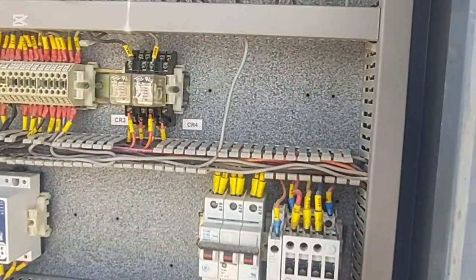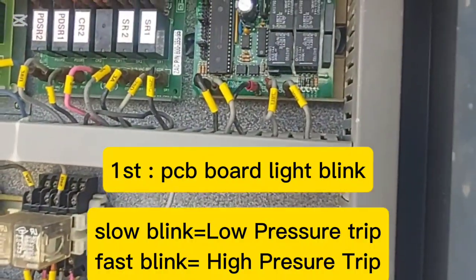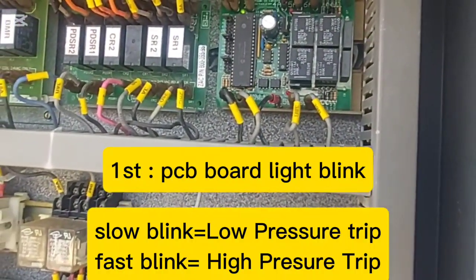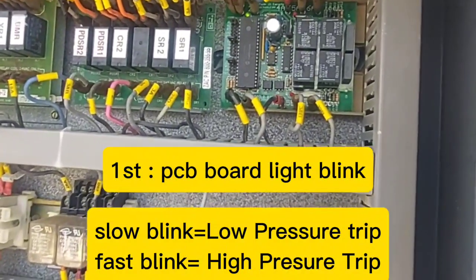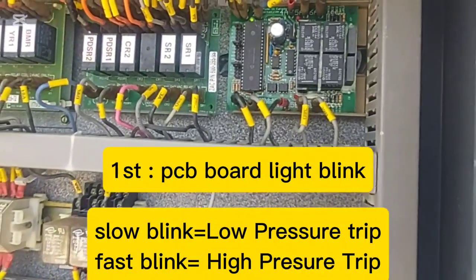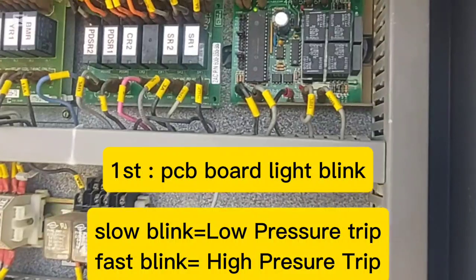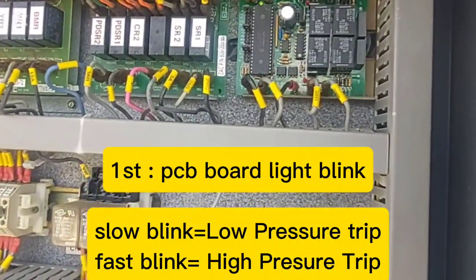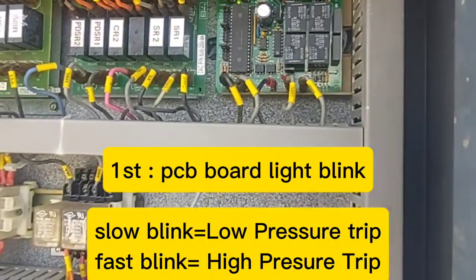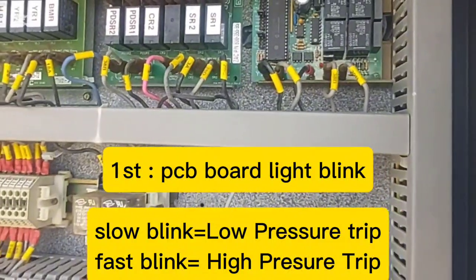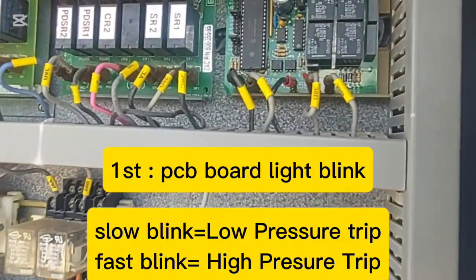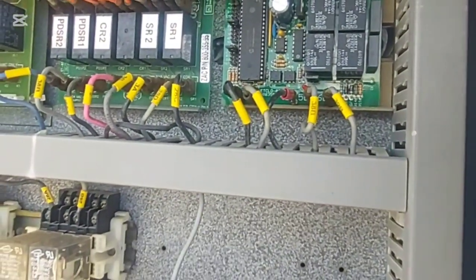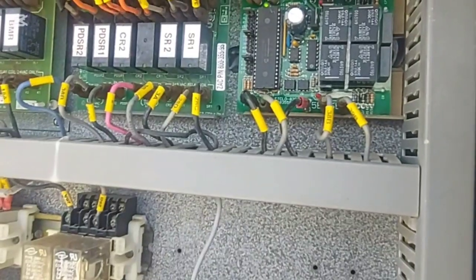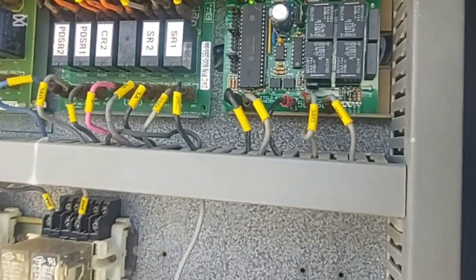If in case any alarm is blinking, if the light blinks fast, it is HP. When the light blinks slow, that time it is LP. This is a function of the PC board. If in case LP, that time the light blink is slow, and if in case HP, that time the light blink is fast.